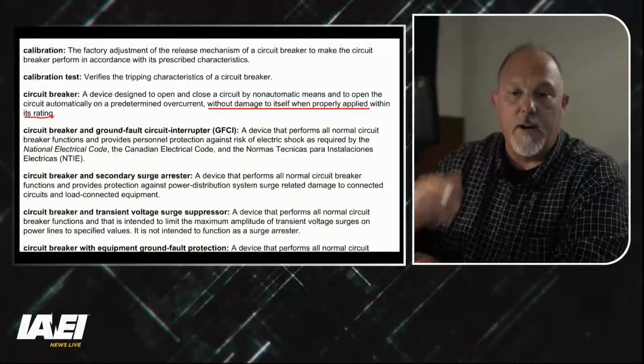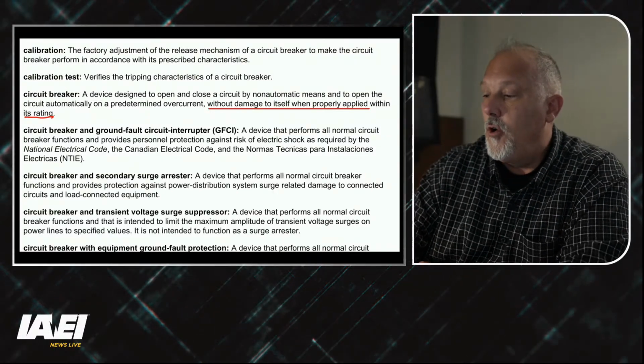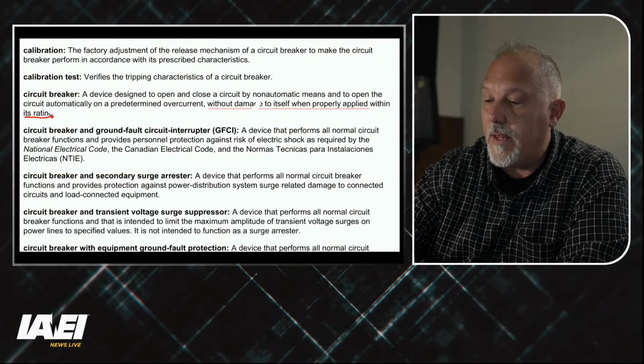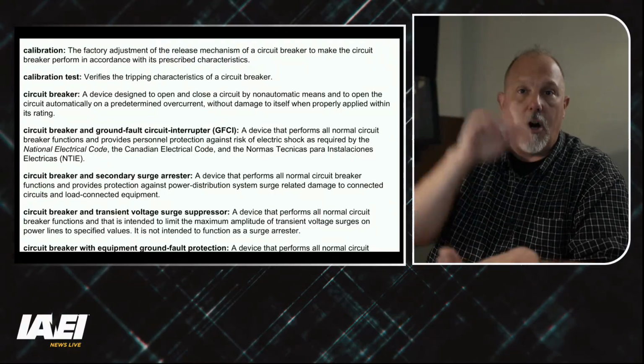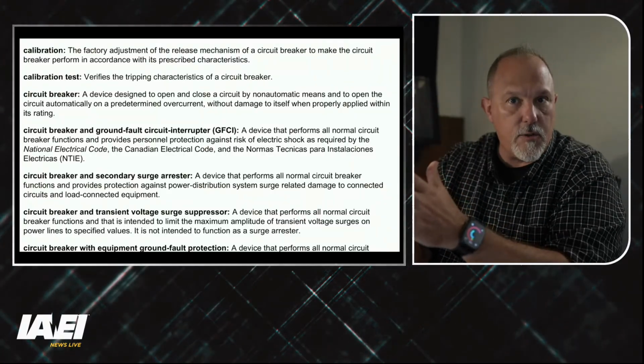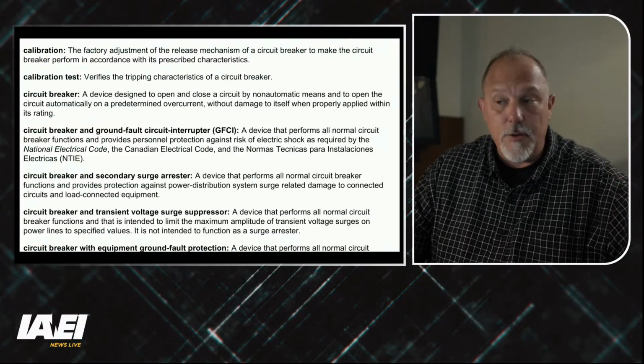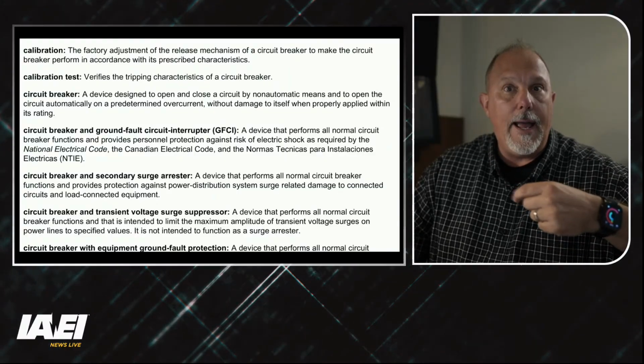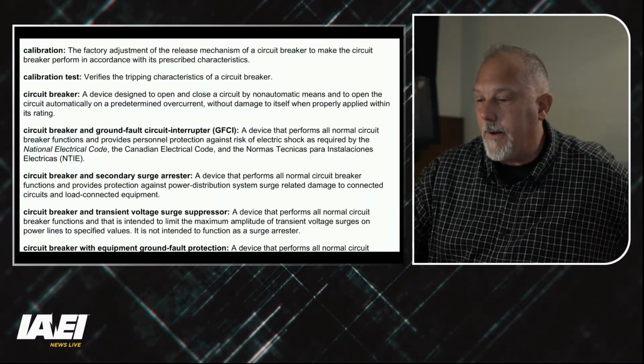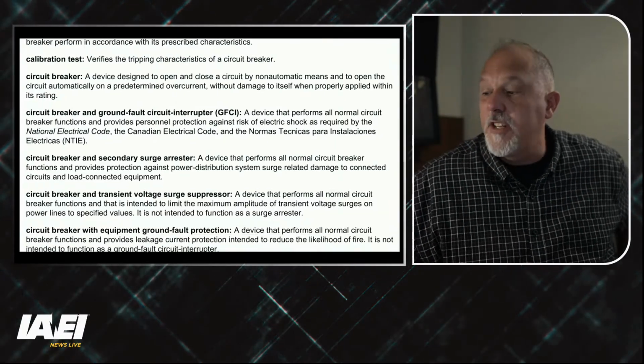So what I like about this document is it gives us a perspective from a NEMA perspective on circuit breakers, specifically molded case circuit breakers, and you've got to think about the scope of the document as well. All right, so we know what we're dealing with with a circuit breaker. It's going to automatically open based upon its time current characteristic curve, and I need to be able to manually open it at my discretion.